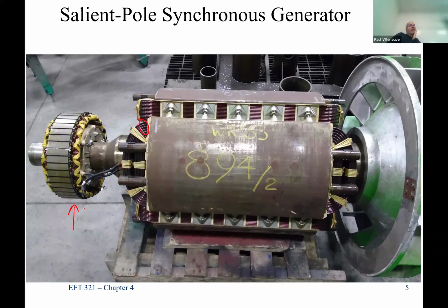It's another synchronous generator, a completely separate one. But remember, we have to get DC into the rotating part, notice there are 2 wires here. I talked about using brushes and slip rings to do that. You can also get better applications where you basically tack on another synchronous generator, but flip it around, so instead of the stator having the AC output, the rotor has the AC output.